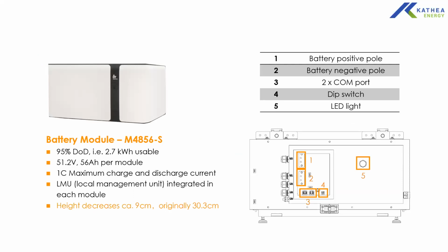So the battery module is called M4856S. It's a lithium battery, just like Alpha, with a longer lifespan of approximately 20 years as well, calendar years. It's a 95% depth of discharge, 2.7 kilowatt hour battery. It's a 56 Ah battery. So you can actually draw 2.7 kilowatts peak power from the battery at a 1C rate. It's a 1C battery. And then it has an integrated LMU.